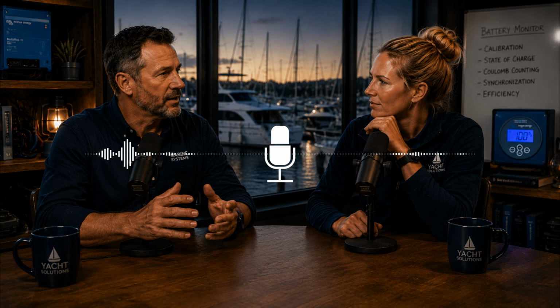So what happens if a user upgrades their system from an old 200 amp hour battery bank to a massive new 400 amp hour bank, but they completely forget to update that number in the app? Well, the monitor will still firmly believe it is managing a 200 amp hour system. As you use power, it will count 200 amp hours going out and confidently declare the battery completely dead at 0%, meanwhile in physical reality your massive new 400 amp hour battery is still sitting at a very healthy 50% capacity.